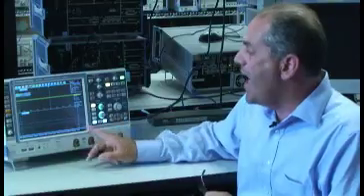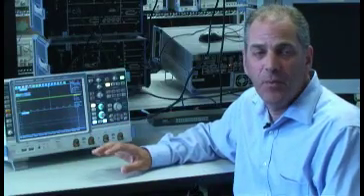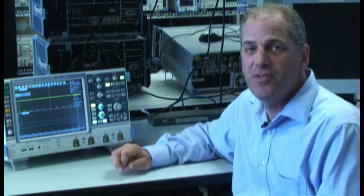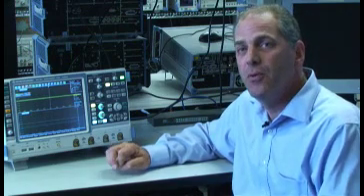The other point you can see here again is this is zero gigahertz, and this is two gigahertz. At the one millivolt per division range, we're still operating at full bandwidth on the instrument. There's no bandwidth limiting. Many oscilloscopes will actually limit the bandwidth on these low volts per division settings as a way to reduce the noise.